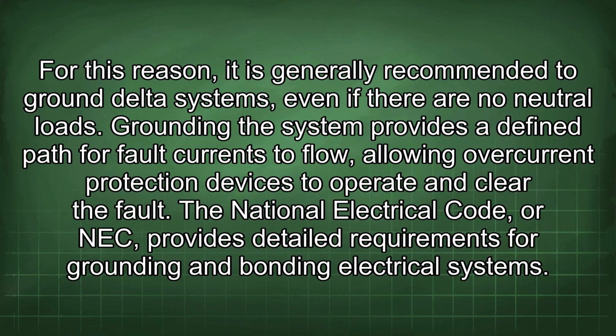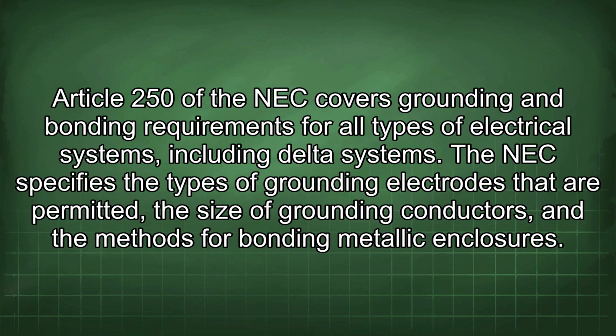The National Electrical Code, or NEC, provides detailed requirements for grounding and bonding electrical systems. Article 250 of the NEC covers grounding and bonding requirements for all types of electrical systems, including delta systems. The NEC specifies the types of grounding electrodes that are permitted, the size of grounding conductors, and the methods for bonding metallic enclosures.